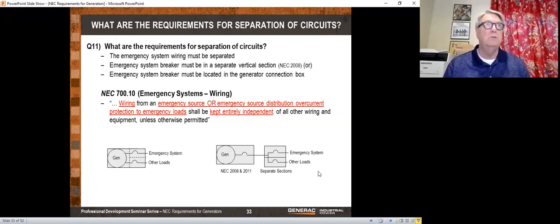And if you have an emergency system and other loads, you'll have the emergency breaker on one side of the generator, and the other side of the generator will have the other breaker. So not only are they isolated metallically, but they're a long ways apart.